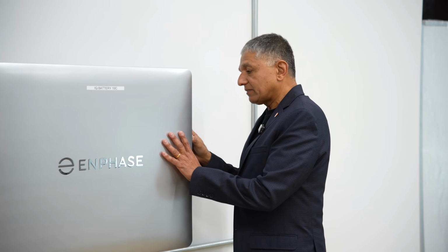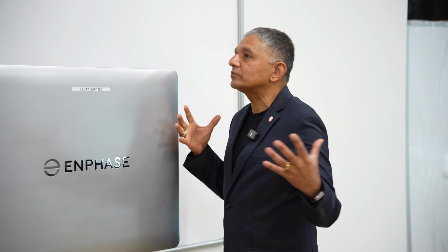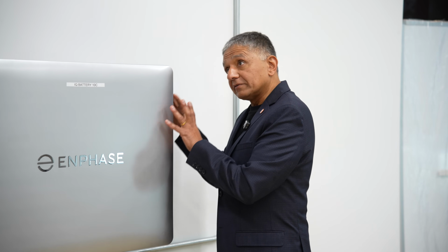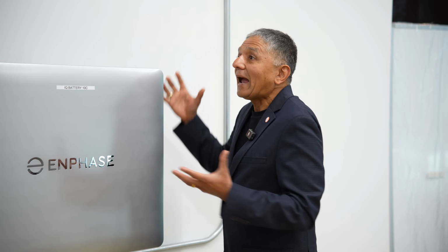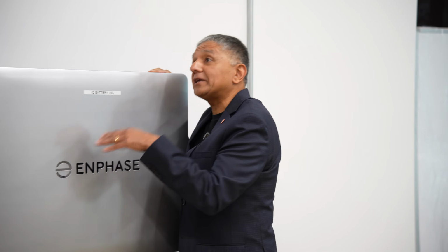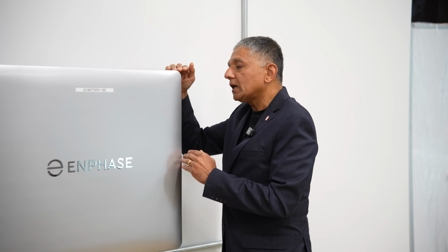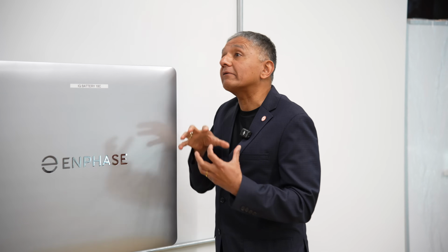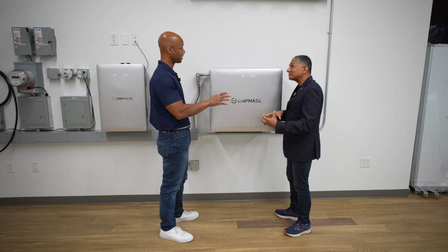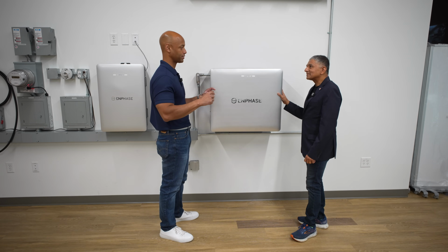The way we accomplished that was by doing what Enphase does best, which is greater integration. We took the power conversion unit and made it bigger. In the prior generation product we had a separate battery management system, and we integrated that into the power conversion itself. This was another issue we were getting back from the field, since each battery had its own BMS, you get a higher idle draw just to have it turned on.